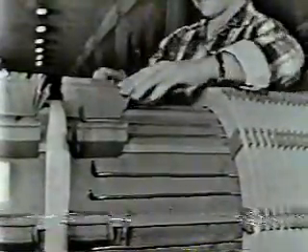Those are spacers he's putting in between there? Yes, Bob, those are the same as the corrugated spacer in a distribution transformer, primarily to let the oil flow between the coils to keep it cool during its operations. The part that it's being wound on, is that an integral part of the coil itself? Yes, Bob, that's a special micarta tube, and that remains there, and that holds the coil in shape and also acts as an insulator between the other coils.